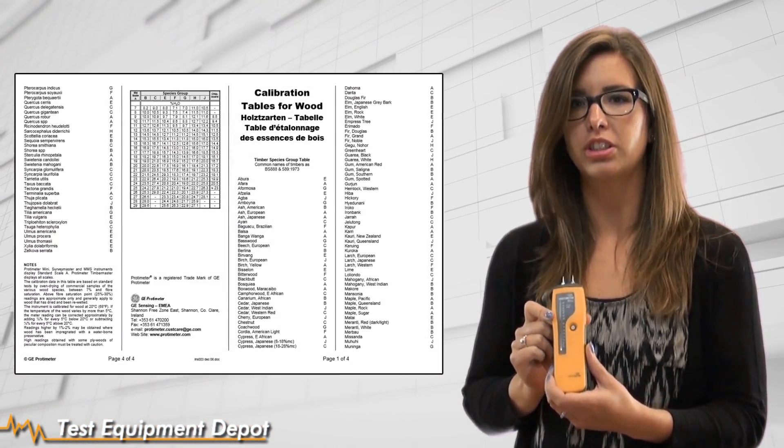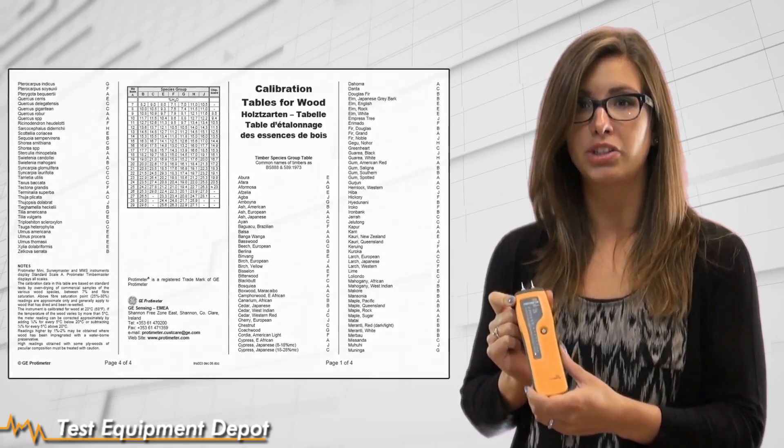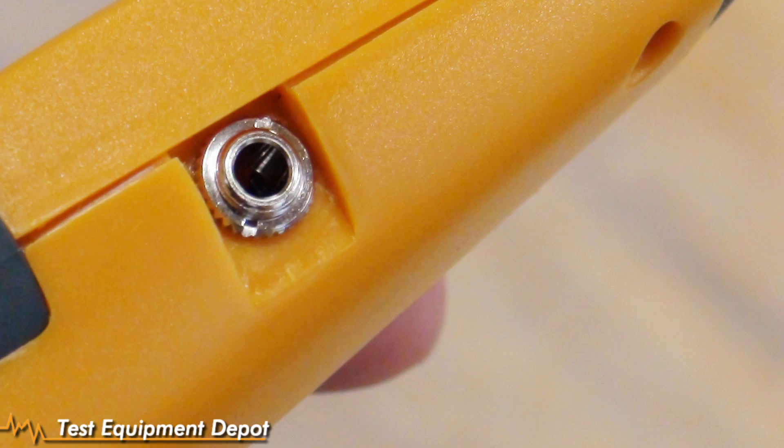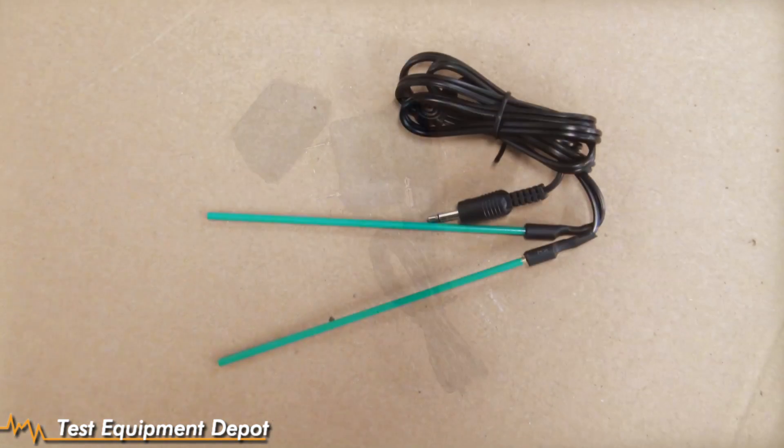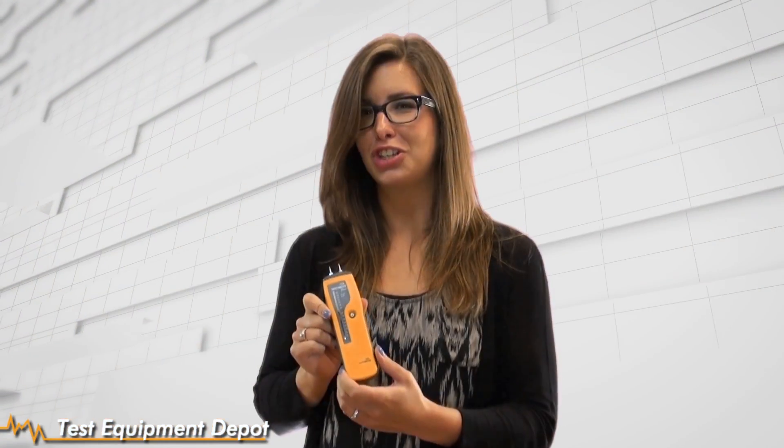It also comes with a wood moisture table so you can specify exactly what species of wood you are measuring if need be. So again, this is our GE Protimeter Mini Instrument, a great pin-type meter. You have a port on the side for a range of different accessories such as a heavy-duty pin probe, deep wall probes, or a hammer electrode if you need one. Thanks for tuning in for a Test Equipment Depot video.